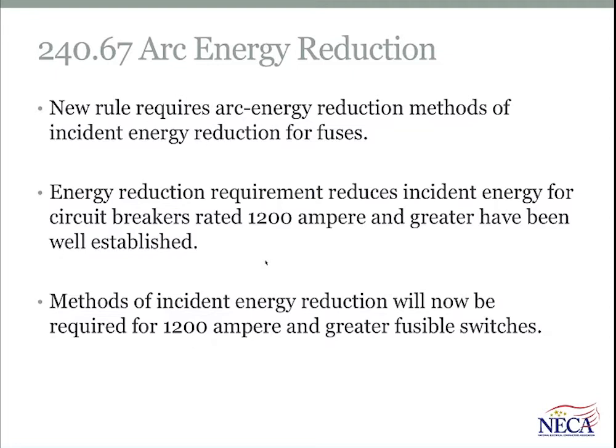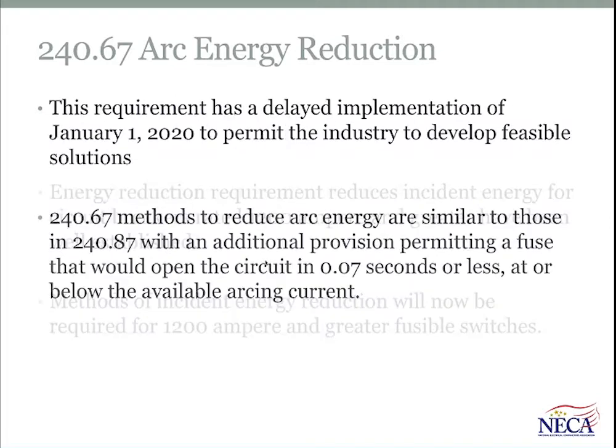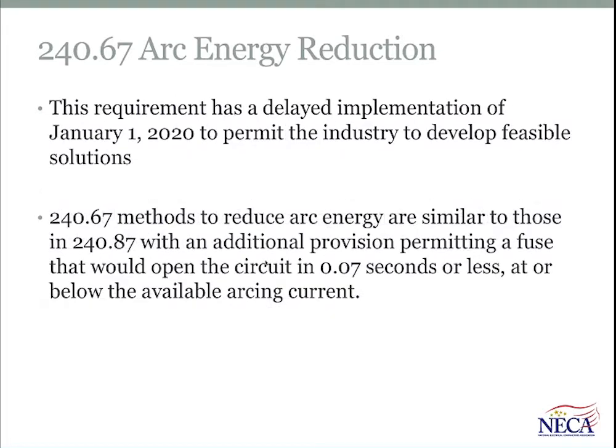Well, new in the 2017 edition of the NEC, the arc energy reduction methods now would apply to enclosures that contain fuses. In other words, fuses, in addition to circuit breakers, can be used where arc energy reduction is required. The requirement has a delayed implementation date of January 1, 2020 to actually permit and recognize that some manufacturers have to have the ability to ramp up and have their processes be compatible with the new provisions in the NEC.